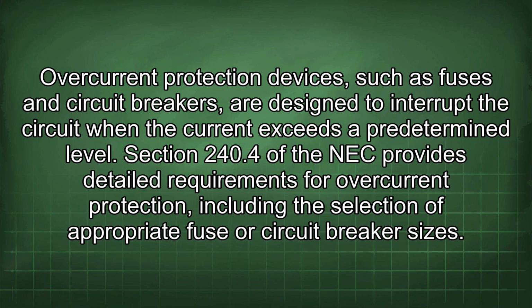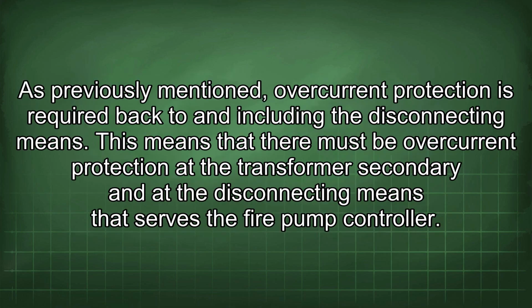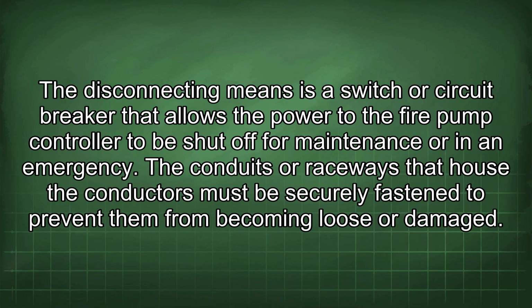Section 240.4 of the NEC provides detailed requirements for overcurrent protection, including the selection of appropriate fuse or circuit breaker sizes. As previously mentioned, overcurrent protection is required back to and including the disconnecting means. This means that there must be overcurrent protection at the transformer secondary and at the disconnecting means that serves the fire pump controller. The disconnecting means is a switch or circuit breaker that allows the power to the fire pump controller to be shut off for maintenance or in an emergency.